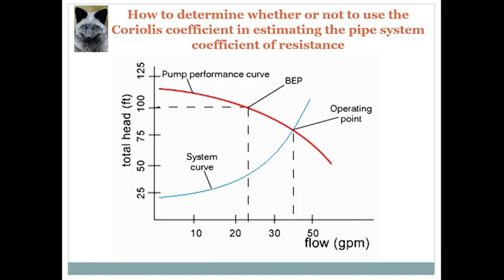For the determination of a pump operating mode, it's necessary to know its operating point at the current operating conditions. The operating point is the intersect between the pump head curve and the pipe system resistance curve, the red and blue lines respectively, like shown in this simple diagram.